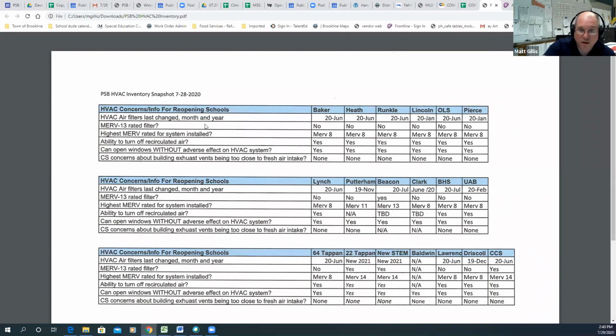In short, you can see when the filters were last changed, and whether it's a MERV 13 rated filter or higher. Air filters in buildings have a MERV rating for what level of dust, allergens, and other materials the filter can catch. They range from 1 to 17, and 13 and higher is high enough—dense enough—to catch particles small enough to be associated with a virus. Most people have heard of a HEPA filter for a vacuum, or occasionally in a car, which would be about a MERV 16 or 17 rated filter.